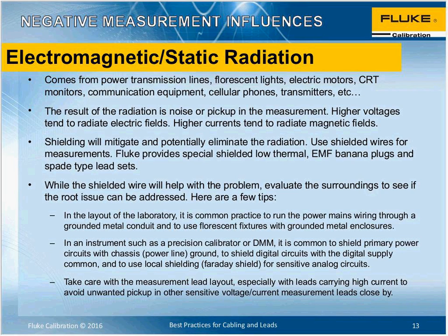Think of the test you're doing. Do you need all that instrumentation there? One way to check if you've got some interference problem from radiated pickup is to make some measurements of some low-level AC signals of a few millivolts and see if you have any problems.